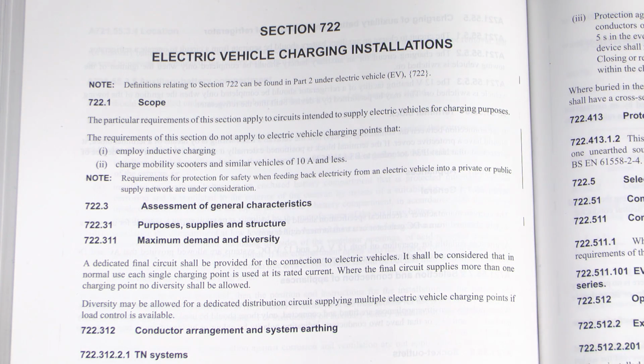Now, say a 32 amp circuit is the most common for a domestic installation, although you can put in, say, 16s, and other ratings, of course, are available. For domestic, it's not going to normally be above 32, mainly because the supply to the building is obviously limited to a fairly small value. And bearing in mind, whatever you're adding here is going to be in addition to whatever loads the property already has. So again, it's obviously 32 is generally around the maximum sort of level that you're going to be installing.